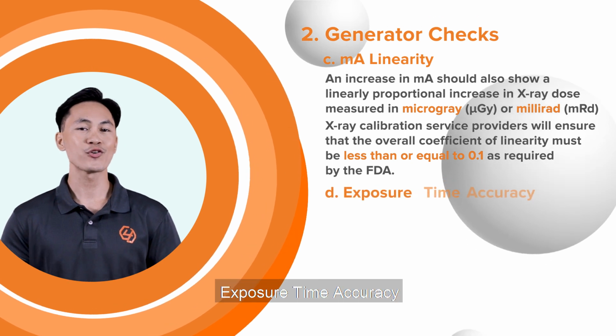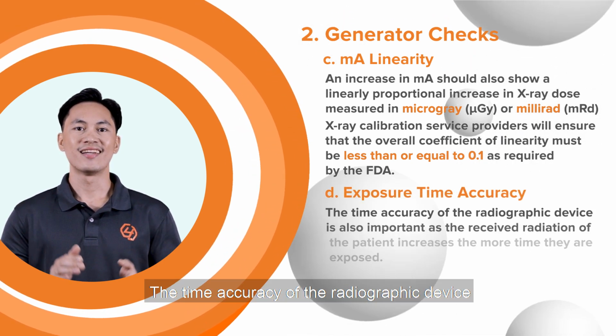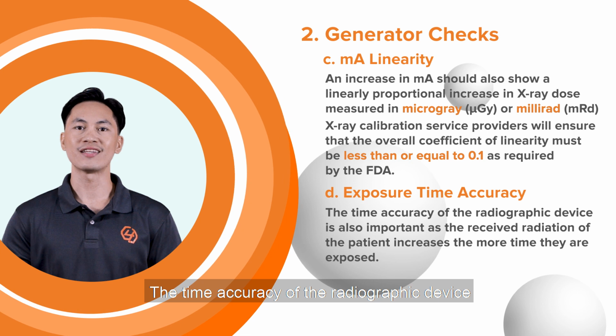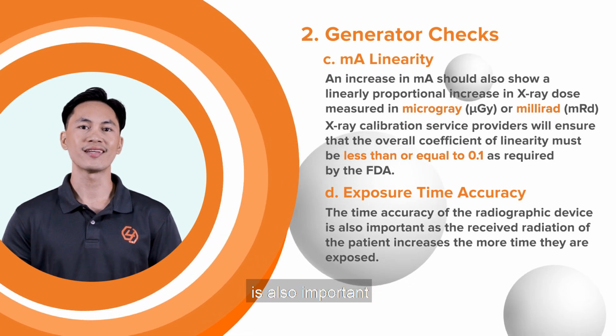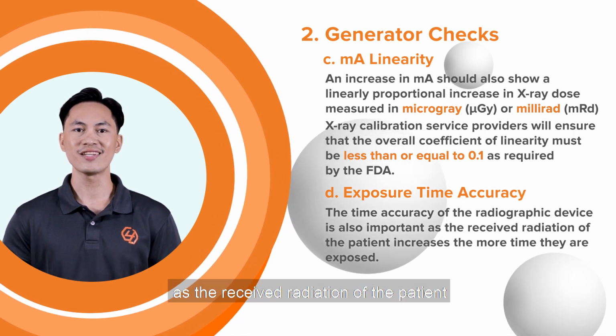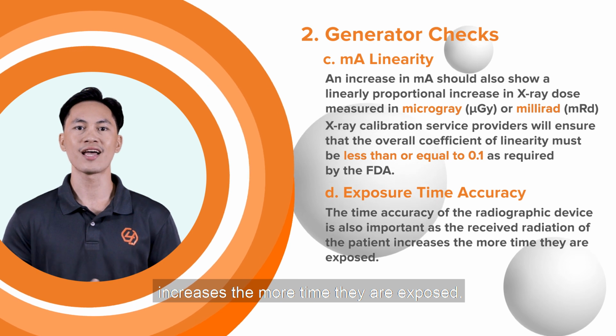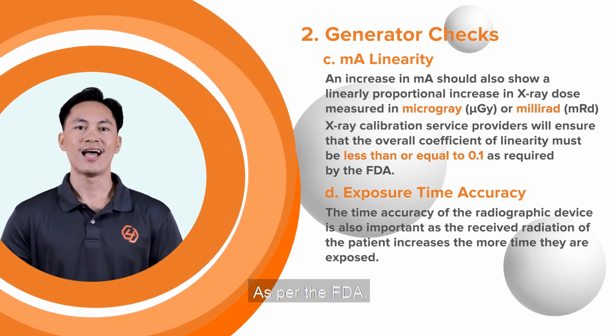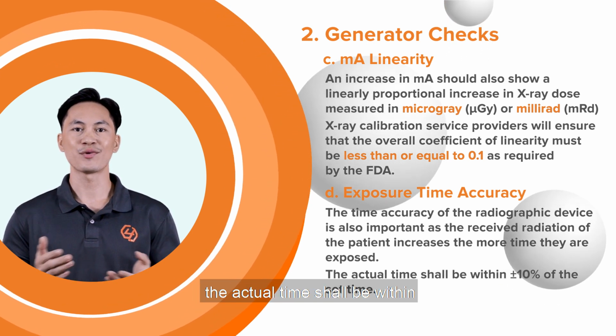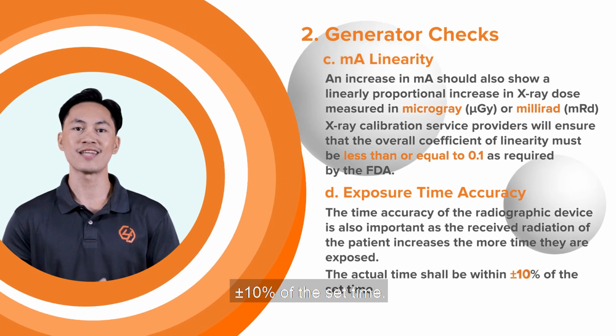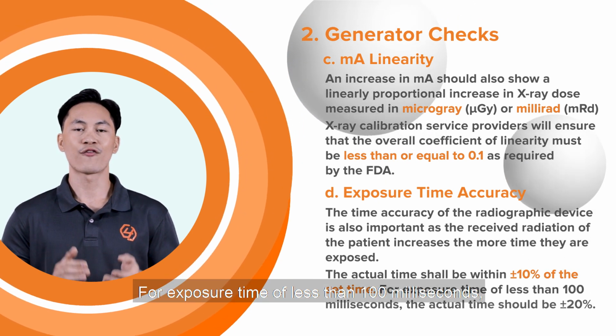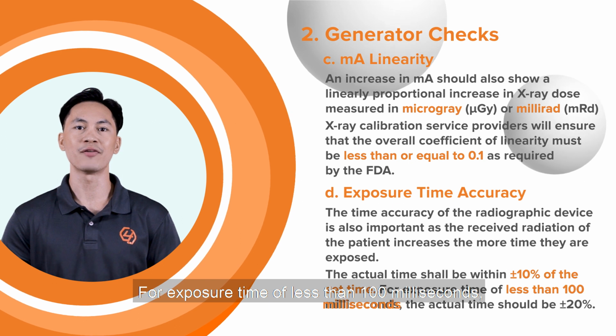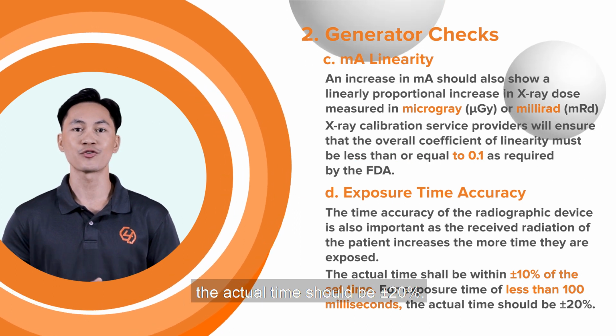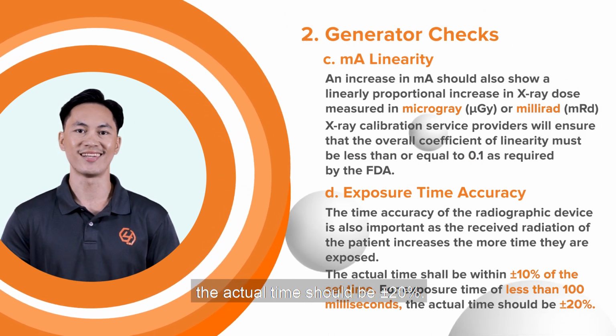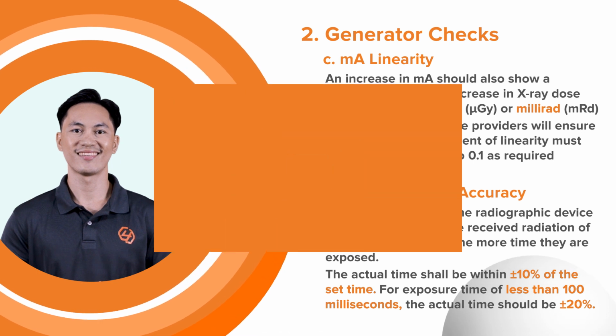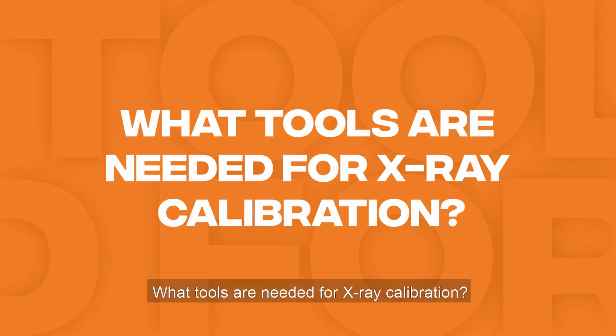D. Exposure time accuracy. The time accuracy of the radiographic device is also important as the received radiation of the patient increases the more time they are exposed. As per the FDA, the actual time shall be within plus minus 10% of the set time. For exposure time of less than 100 milliseconds, the actual time should be plus minus 20%. What tools are needed for X-ray calibration?